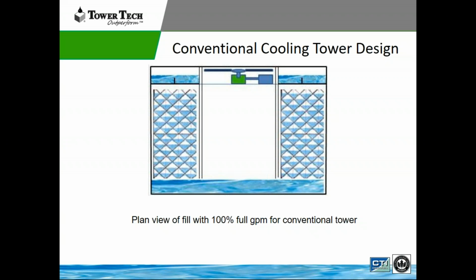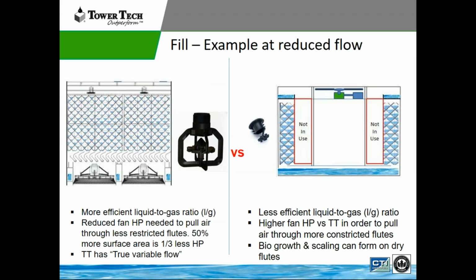Where we're getting our energy savings is right here. At part flow, let's say we're running at 50% flow, we are covering all of the fill with half the flow. The efficiency on a cooling tower is pretty simple. You need surface area to cover. If you can cover that fill with as much surface area as possible, at that point I could reduce the fan speeds of the direct drive fans. Then we save significant energy. On a traditional system, you look on the right-hand photo.